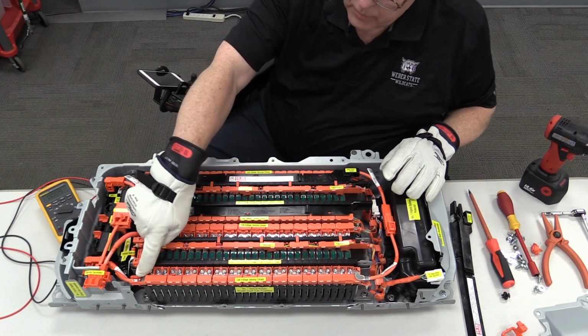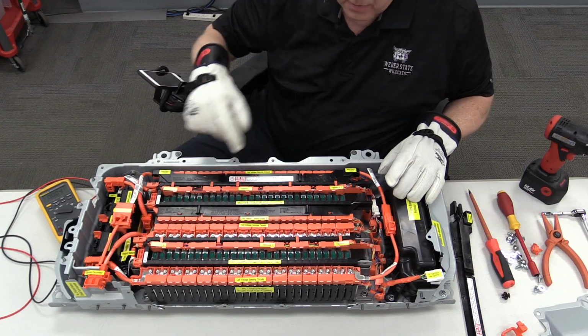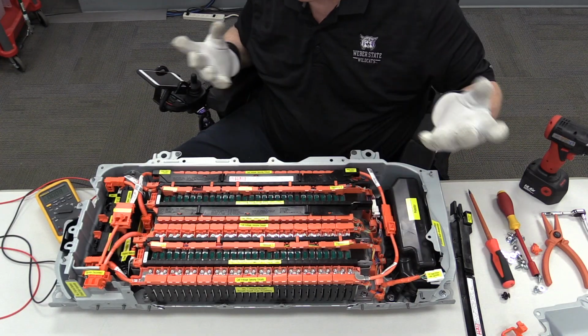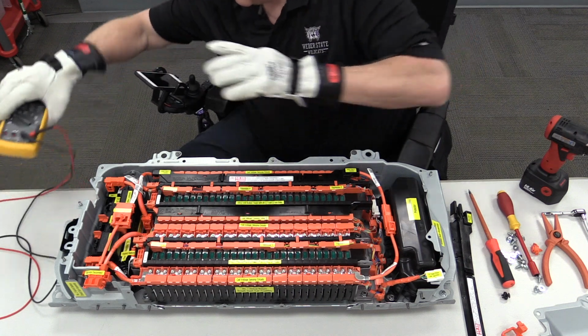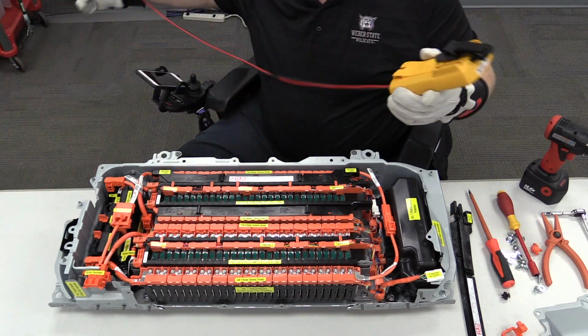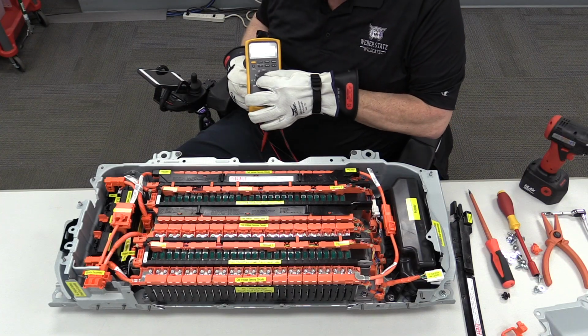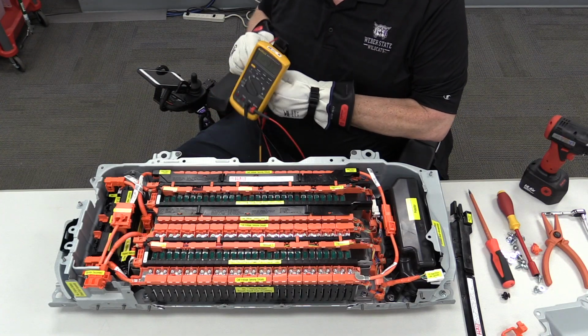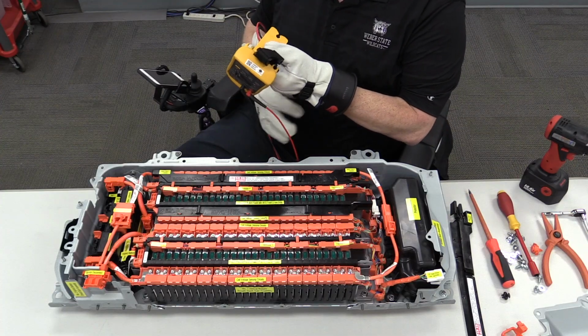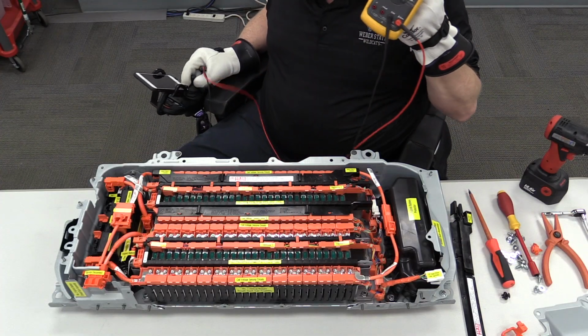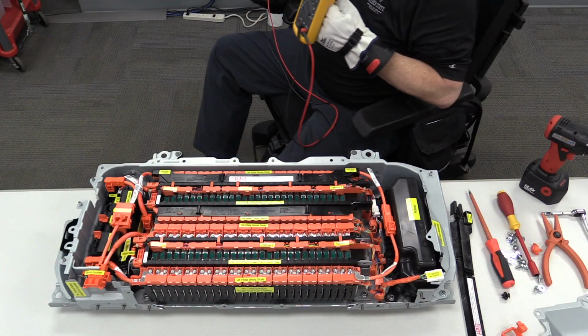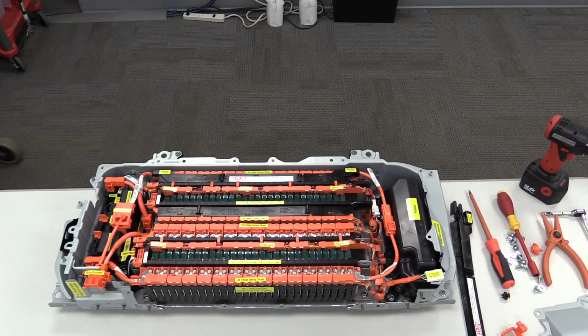All right, with both covers removed, you can see the full set of studs straight across for each 3.7 volt battery cell. Now, let's take some voltage measurements. We put our voltmeter on DC volts, and let's check it on another voltage source just to make sure our meter leads are good. I've got a 12 volt battery just to ensure our leads are good and our meter is working like it should. 12.77 volts, so we're in good shape.